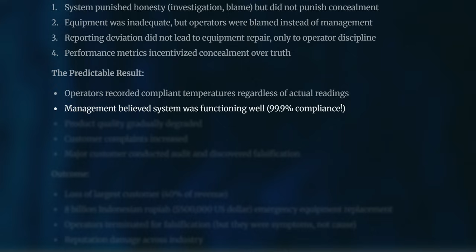Now, the following is the system failure. First, the system punished honesty with investigation and blame, but did not punish concealment. Also, equipment was inadequate, but operators were blamed instead of management. And reporting deviation did not lead to equipment repair, only to operator discipline. And performance metrics incentivize concealment over truth. So, the predictable result here is the following. First, operators recorded compliant temperatures regardless of actual readings. And management believed the system was functioning well at around 99.9% compliance. Product quality gradually degraded as a result.